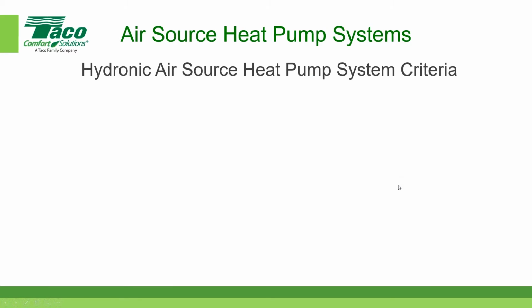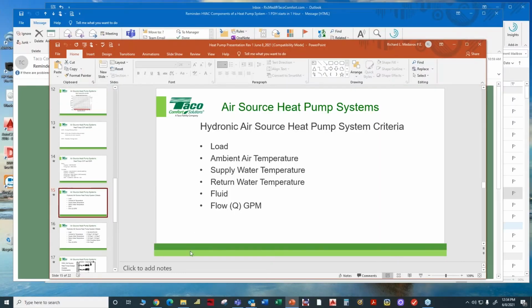system criteria. We're going to design an air source heat pump system, but we have to establish some of the criteria. In this case, we have to establish what the load is, and you get that from a heating and cooling load calculation. We always recommend that you do a detailed heating and cooling load calculation. And if you need some software to do that, you can get that from us. Actually, I'll show you where to get it quickly.